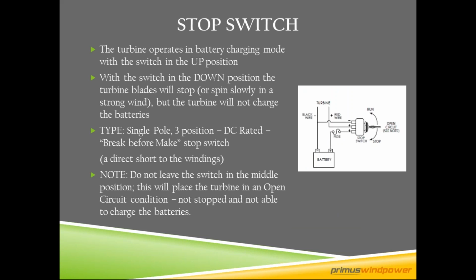When you go out to the site to do annual maintenance or check on the turbine, it's good to stop the turbine with the stop switch. It's a direct short to the windings, so you can do your maintenance. It's also good for a hard reset of the circuit card, an electronic component. If you have to turn the turbine off for any other reason, like big storm conditions, it's a good idea to have that stop switch in line.